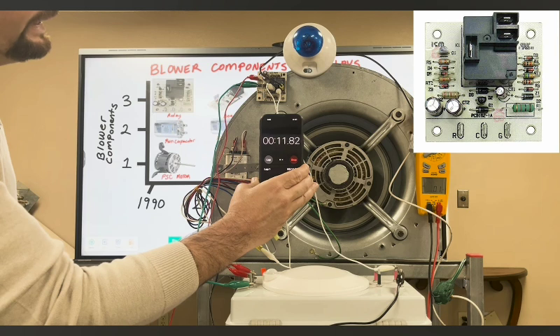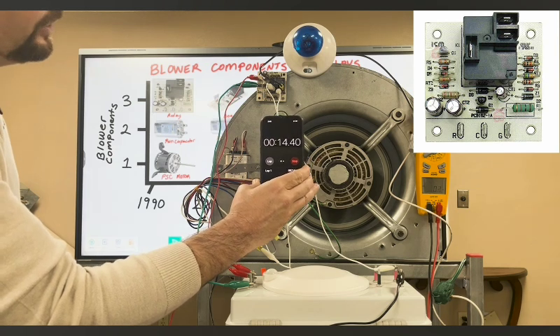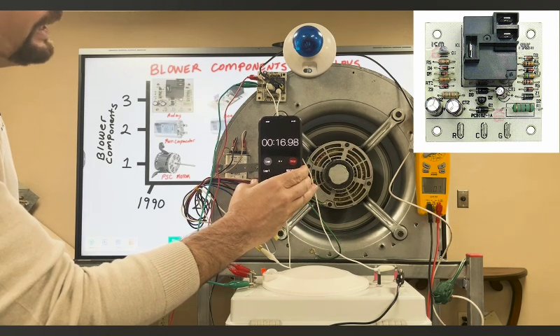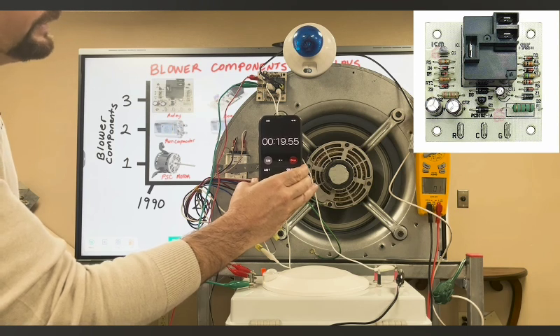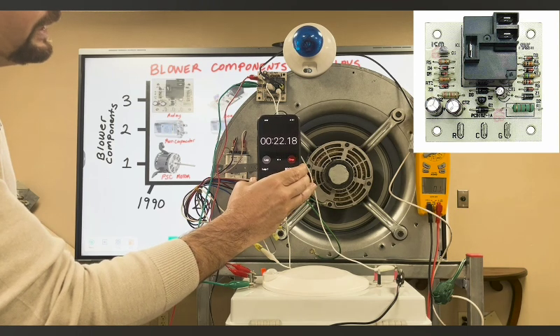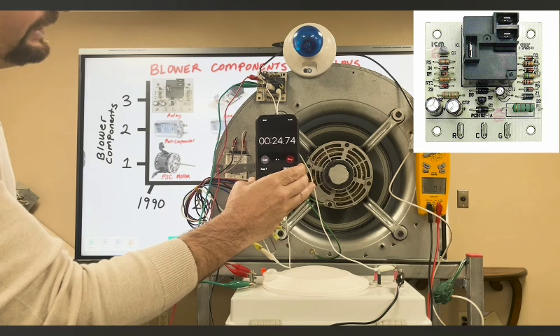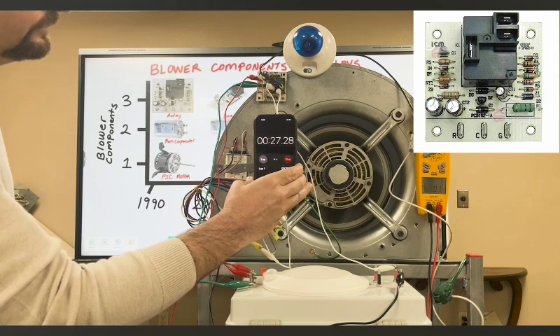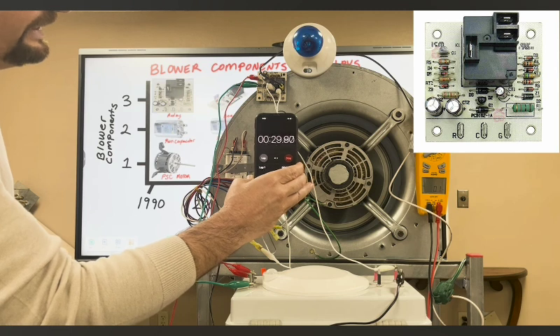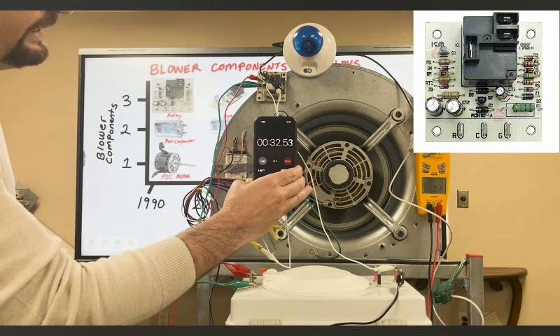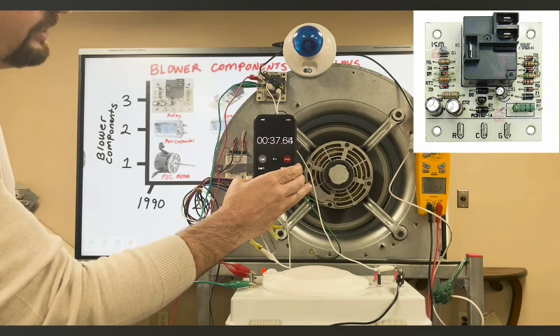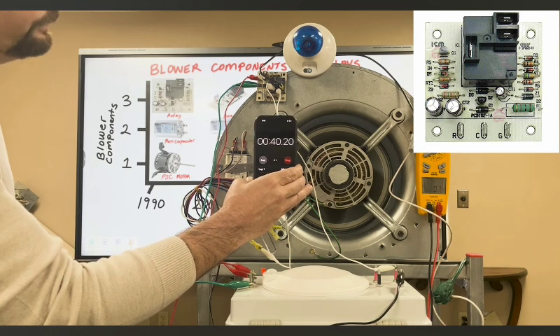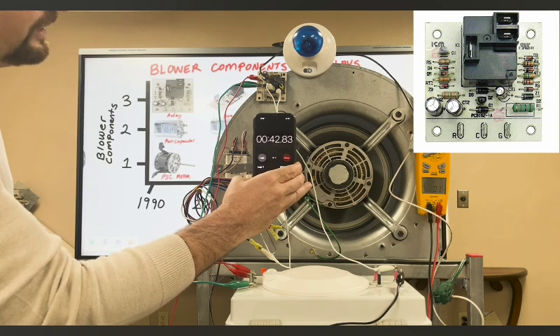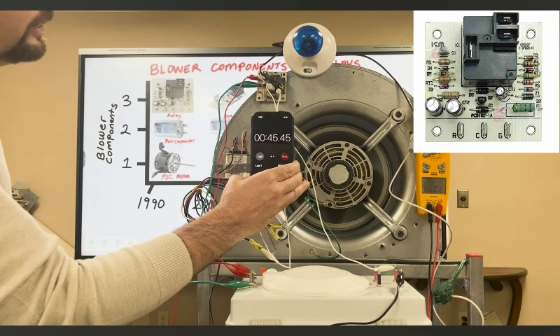So this is an off delay, so we just lost the G call, meaning the condenser is probably satisfied from the thermostat, it's cycled off. There's no G call coming from the thermostat, but the only thing that's running is the blower motor. And you're familiar with this already on your ICM motors, where they delay on and delay off for a little bit. And we were doing that with PSC motors long before the ICM motor came out. So this is the same technology, same thinking, just a delayed on off.